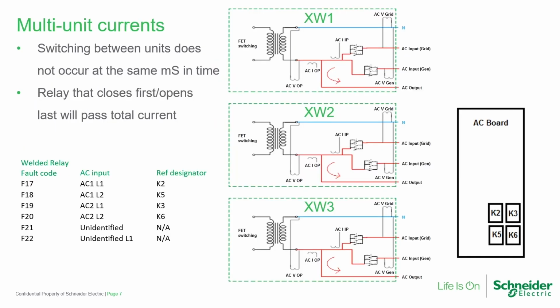When a multi-unit system qualifies or transfers an external source of AC, the input and the output terminals are common. Welded relay faults can occur when the load is excessive or if there is a loop from input to output. More than 100 amps will usually weld the relay closed. The reason for this is that they don't all close their respective internal relays at the same moment in time. It may take up to a half a second between when the first transfer relay closes and when the last one closes. So this differential causes the first relay that closes to have total current across it. If the relay is welded, the fault may clear should the relay become unstuck. However, this means there is a problem that must be addressed.